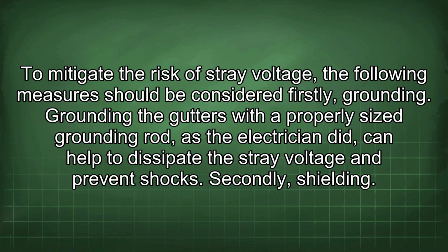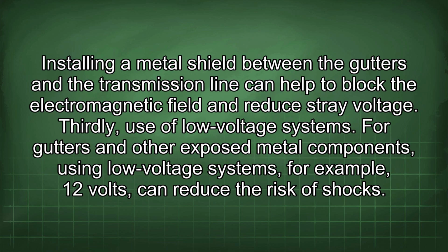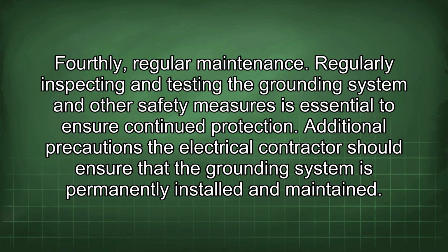Firstly, grounding. Grounding the gutters with a properly sized grounding rod, as the electrician did, can help to dissipate the stray voltage and prevent shocks. Secondly, shielding. Installing a metal shield between the gutters and the transmission line can help to block the electromagnetic field and reduce stray voltage. Thirdly, use of low voltage systems. For gutters and other exposed metal components, using low voltage systems, for example 12 volts, can reduce the risk of shocks. Fourthly, regular maintenance.